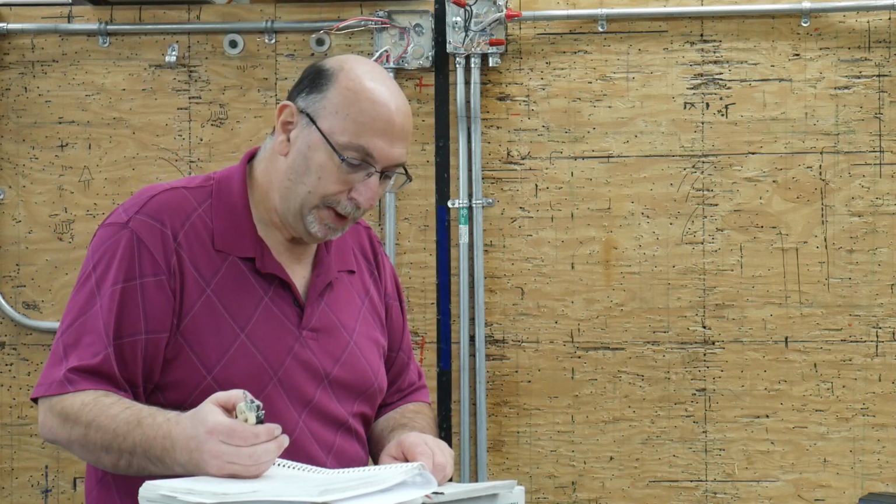Next, sub-rule 3. Where a box contains a device having a dimension greater than 2.54 centimeters, that's for example a dimmer, we have to use this formula, which is 32 centimeters multiplied by the depth of the device. We're going to be showing an example very briefly on the next slide where we are using a dimmer of a certain size, and we have to calculate the box fill. So a key table to remember is tables 22 and 23. We'll be discussing that very shortly.